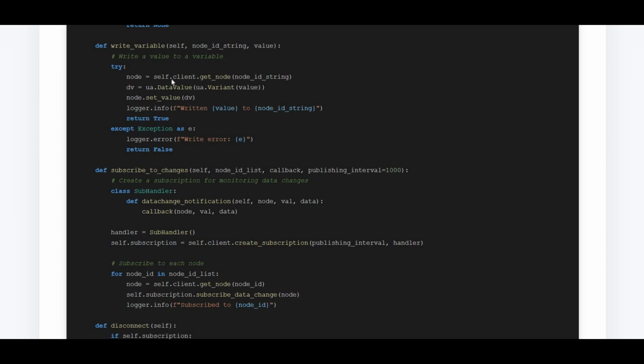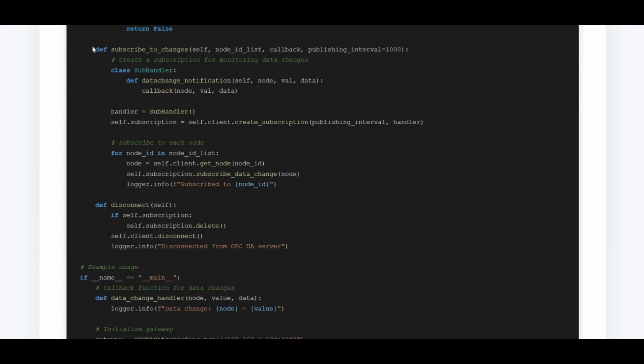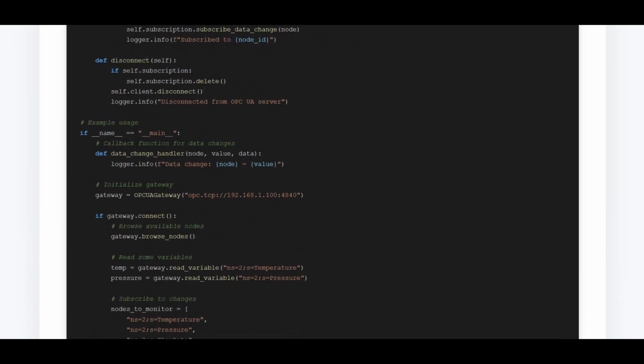Okay, and here, subscriptions are where OPC UA shines. We define a sub-handler class with a data change notification callback. Whenever the server detects a change, this callback fires. We then create a subscription with a publishing interval and subscribe to each node ID in the list. And this shifts the model from polling to event-driven updates. Instead of asking for data every second, the server pushes updates when values change. And disconnecting deletes the subscription and closes the client cleanly.